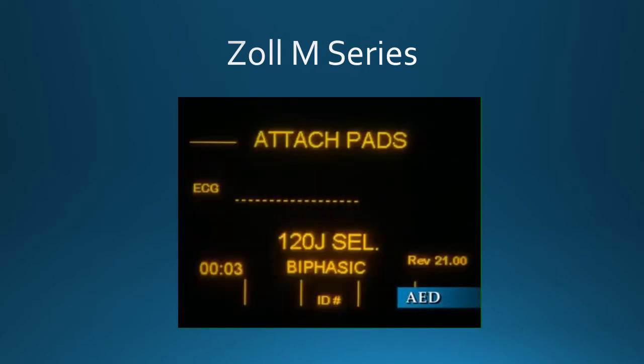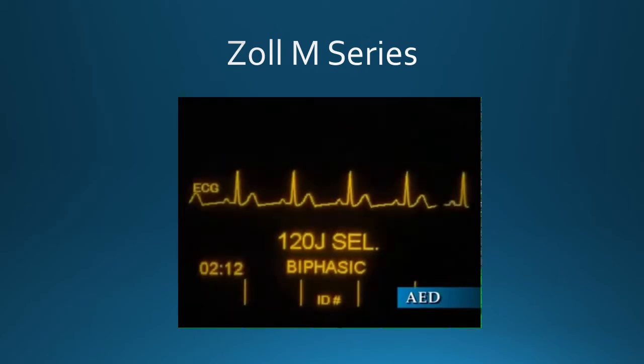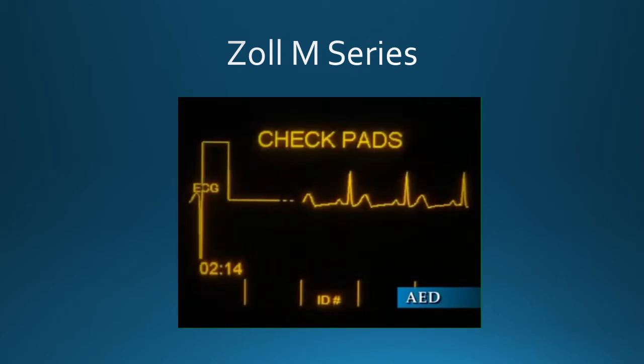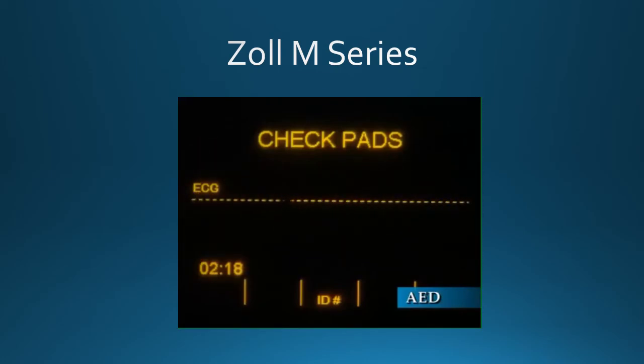Attach pads. On power-up, the message and voice prompt, "Attach pads," will be issued if ECG electrodes or MFE pads have not been attached to the patient. Check pads. If the pads become detached or the connection is broken, a "Check pads" message and voice prompt will be issued.